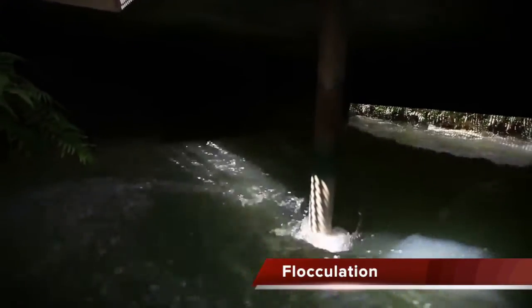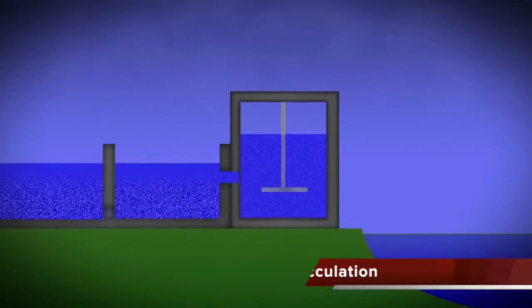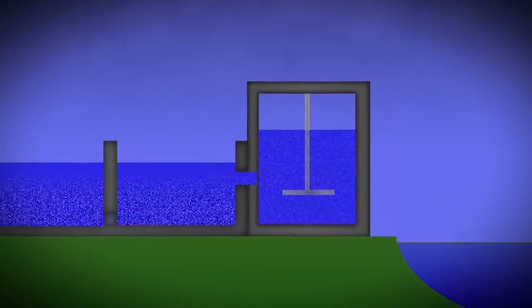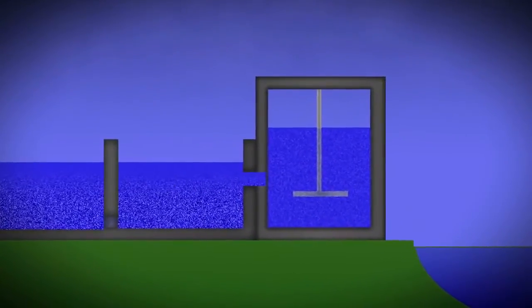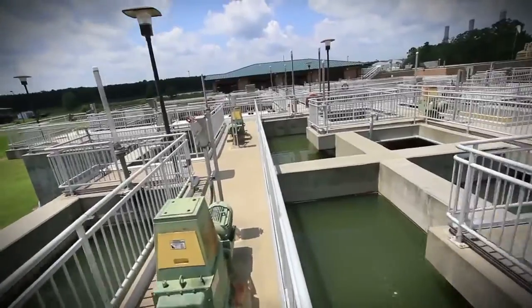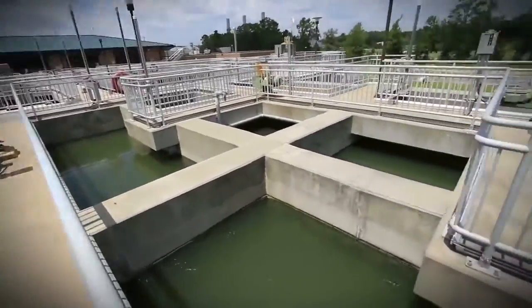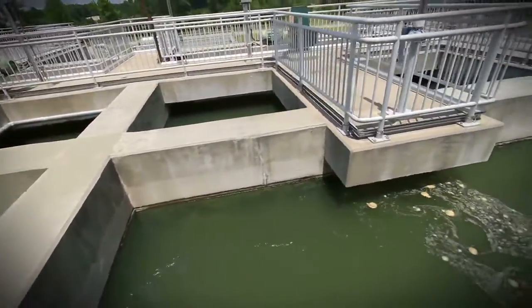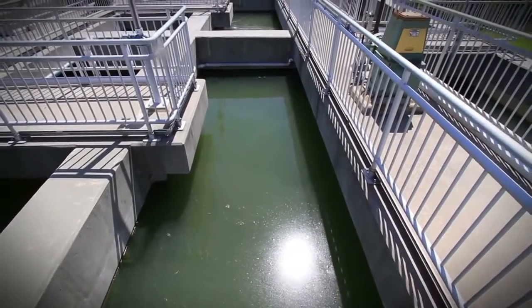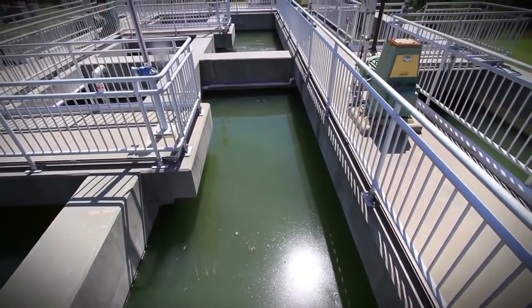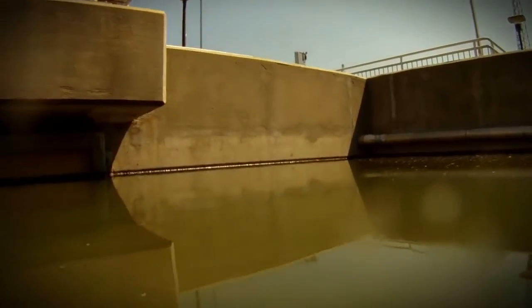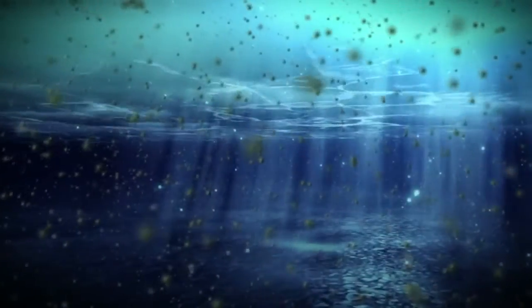Coagulants such as aluminium sulphate are usually added into the water. The flocculation speeds up the settling process. During flocculation, the coagulated particles collide, stick together, agglomerate, and then settle. To avoid them from settling prematurely, gentle mixing is required. The paddle turns gradually to promote the growth of the particles. The amount and total volume of the particles, and the velocity gradient in the basin, affect the speed of flocculation.